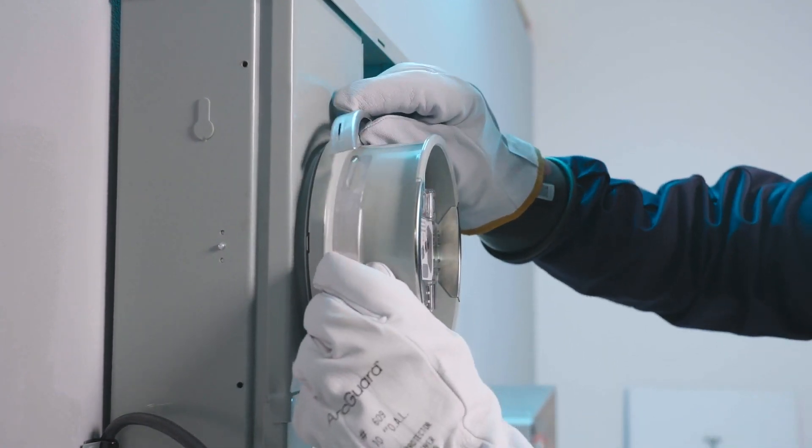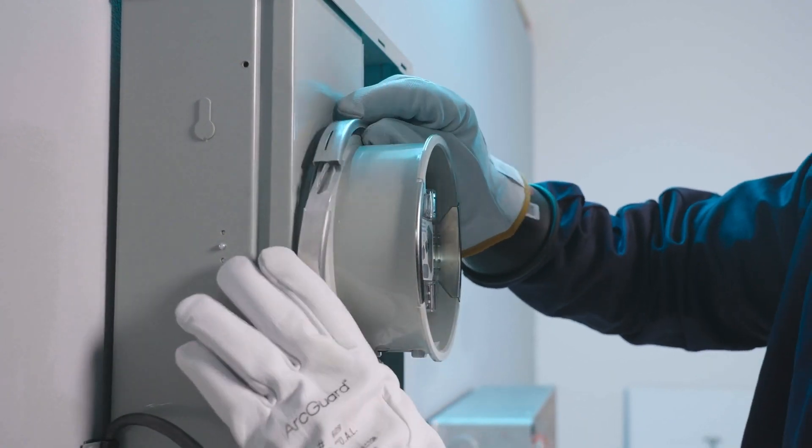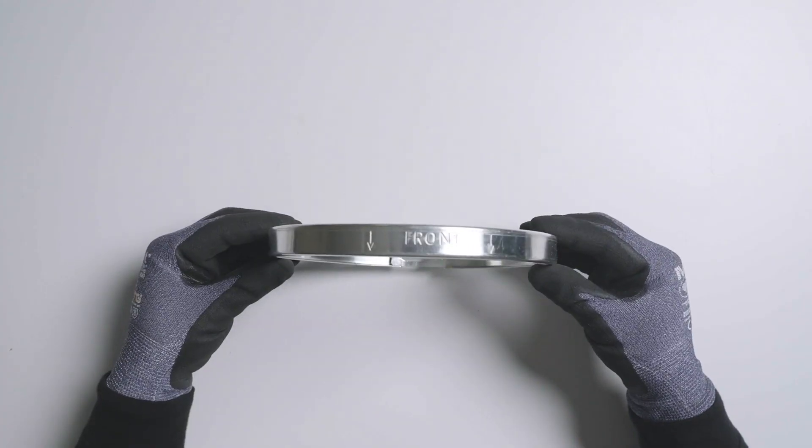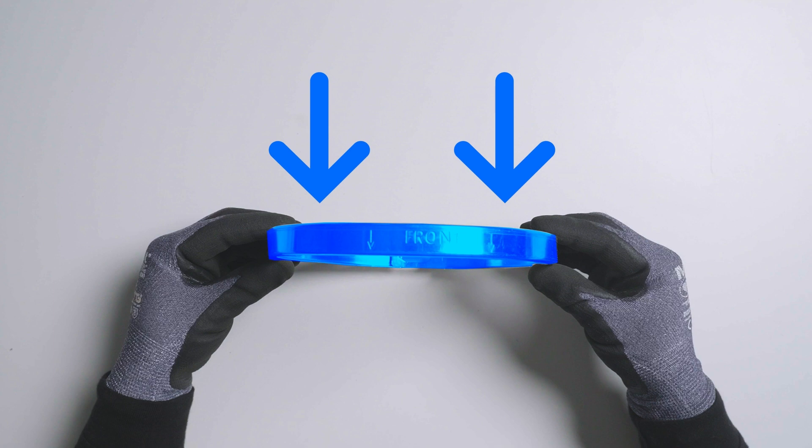For ring-type meter sockets, install the sealing ring to secure Backup Switch to the meter socket. Ensure the sealing ring is oriented so that the front arrow etched into the ring faces toward the meter and not the panel.